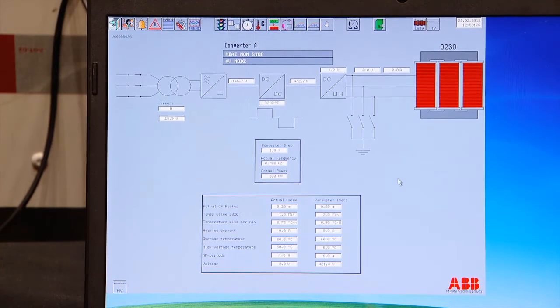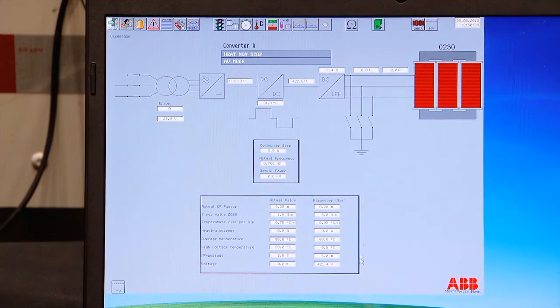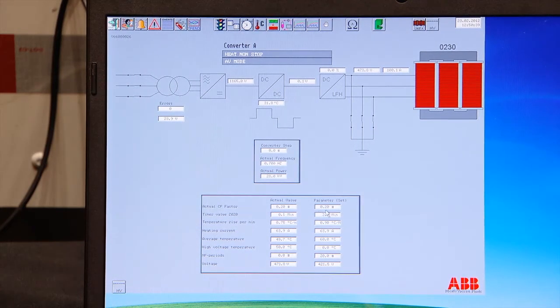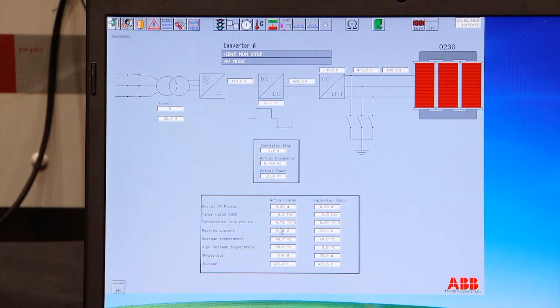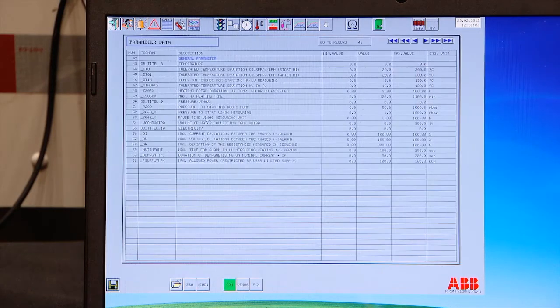What's interesting on this page is to monitor the current factor. The actual current factor is 20% of nominal current. The parameter is 20%, so that's reaching that one. We have the timer, the 2-minute timer. After 2 minutes and 20 cycles, he will adjust the current factor if necessary, based on the temperature increase. We have now set the temperature increase to 0.90. That is a little bit high for what we want, so we reduce that one on the parameter page.